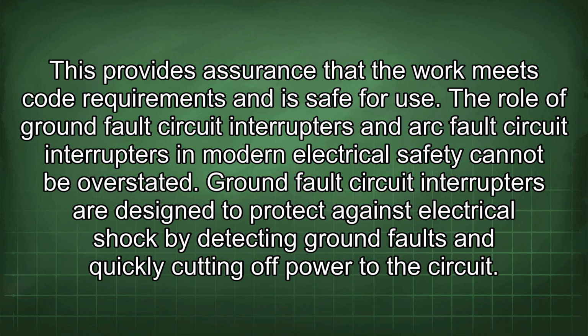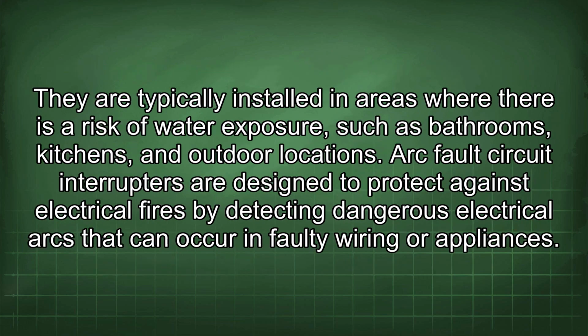The role of ground fault circuit interrupters and arc fault circuit interrupters in modern electrical safety cannot be overstated. Ground fault circuit interrupters are designed to protect against electrical shock by detecting ground faults and quickly cutting off power to the circuit. They are typically installed in areas where there is a risk of water exposure, such as bathrooms, kitchens, and outdoor locations. Arc fault circuit interrupters are designed to protect against electrical fires by detecting dangerous electrical arcs that can occur in faulty wiring or appliances.